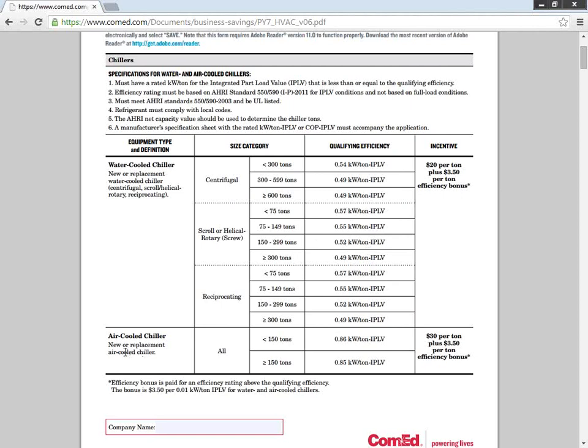There's also a tier for air-cooled. That one is independent of the compressor type that you have. It just matters if you're above or below 150 tons, and then the target changes slightly, either 0.85 or 0.86 kW per ton. And then you get $30 per ton as your rebate.